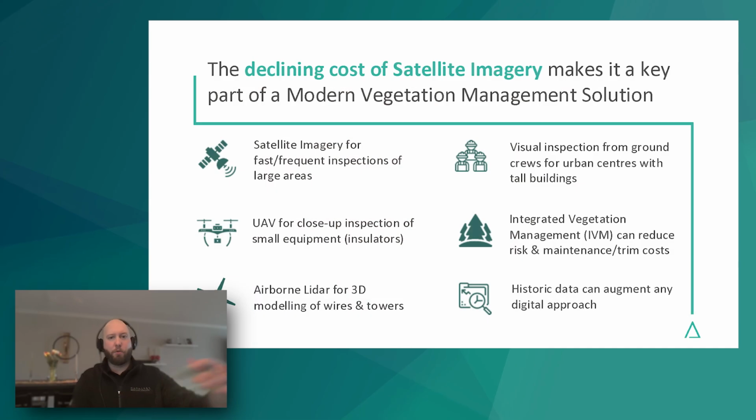With satellite inspections costing 1/3 of ground-based inspections on a per kilometer basis, they can be phased into existing programs without disrupting existing operations and processes and without a large increase to your budget, but still having a very significant impact on the outcome. With the same budget, you could get a high-level inspection of the entire network from a satellite imaging solution and deploy your crews to only inspect the areas that actually need attention that year.